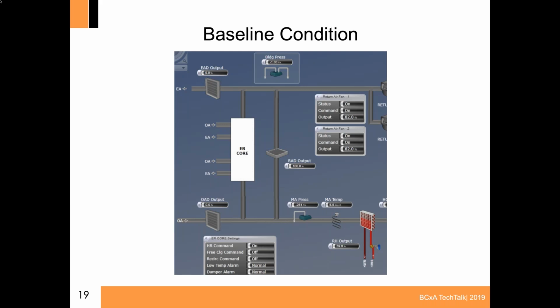So you can see right now, just to the left of that red heating coil, you can see it says MA temp. That's supposed to be mixed air temperature. But knowing where that sensor was placed was incredibly important because it's actually placed right where it comes off of the energy recovery core. So it is not a mixed air temperature. It's actually the discharge temperature from the energy recovery core. And the way we discovered that was one of us was inside the housing right beside the core discharging when it was minus 10 Celsius out. For the first 15 seconds, the air coming off of that was nice and warm, but then it dissipated, and by the end of the 60-second cycle was actually at about minus 10 Celsius. So we knew that the cores were not fully charging.